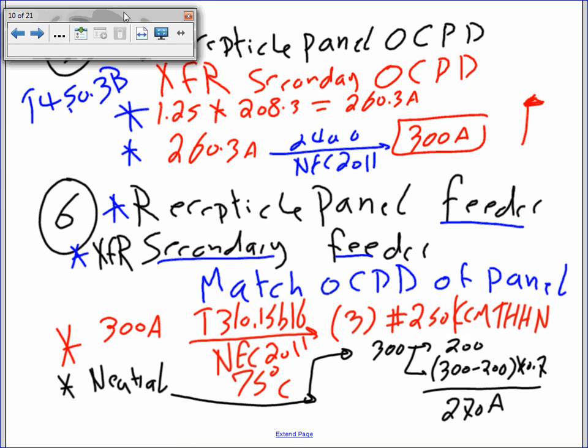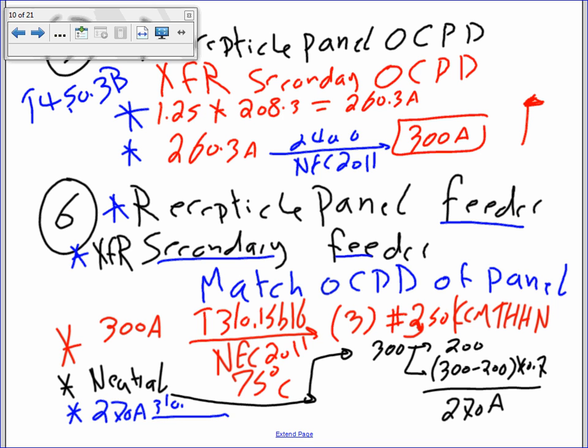Sorry, the 350. I go by the overcurrent device. I'm sizing the neutral. Yeah, the grad should be 350. That leg just dropped. This should be 3. Not 2, this is 3. You got it? 350? Okay, thank you. So the neutral, I need to size for 270, guys. Now, the next step, my friend, is take the 270 and take it to Table 310.15(B)(16), 75-degree column.